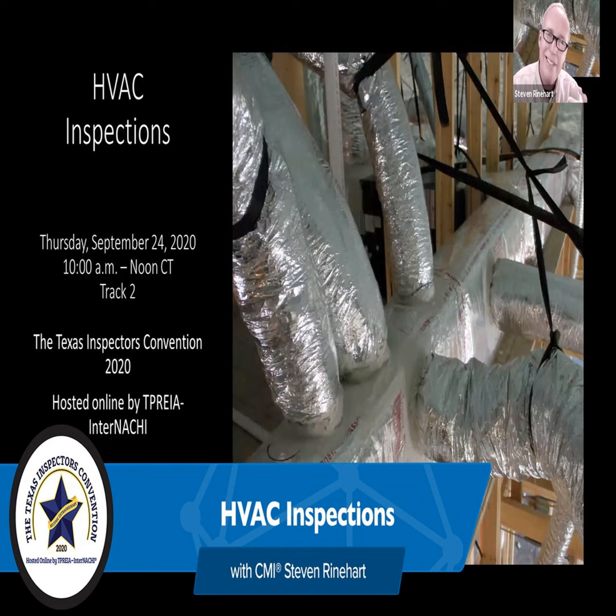But I know the air handler is running. I know the furnace is running. I have no idea about the air conditioner because the condensing unit didn't run. If I didn't have electricity, it's a not inspected because I didn't have power. I'm not saying it didn't work. If I have power at everything and it's not cooling, then we're in that second one.